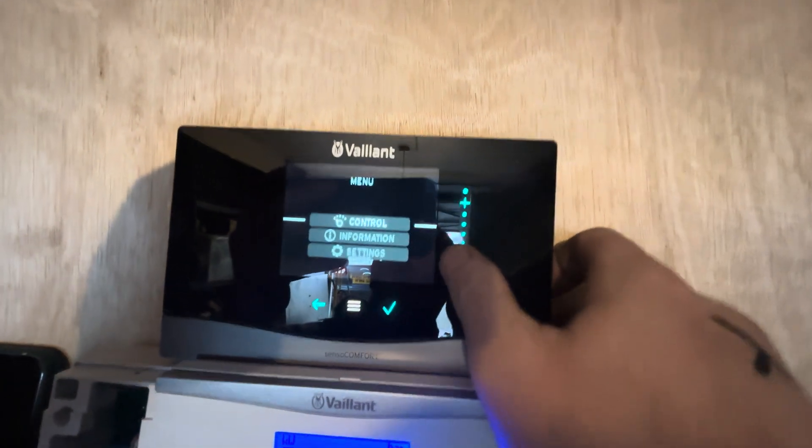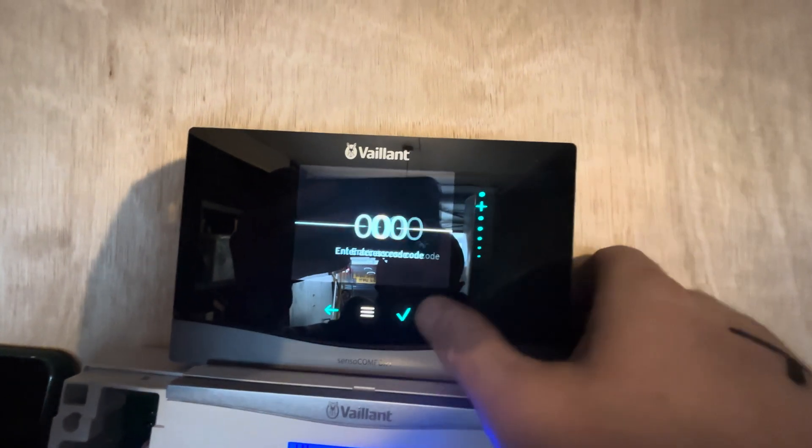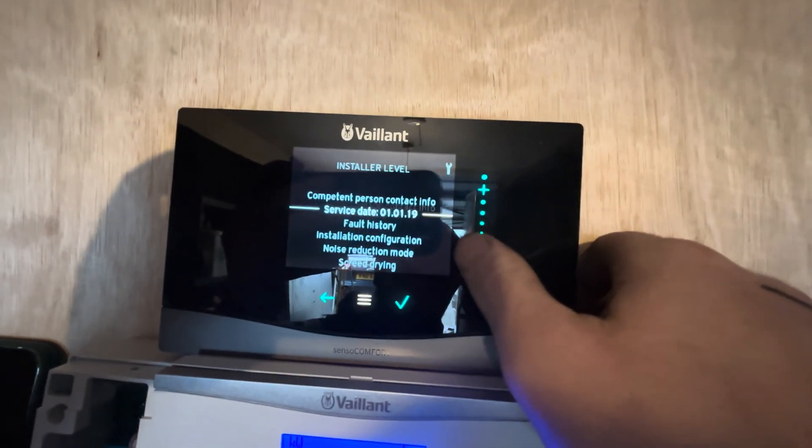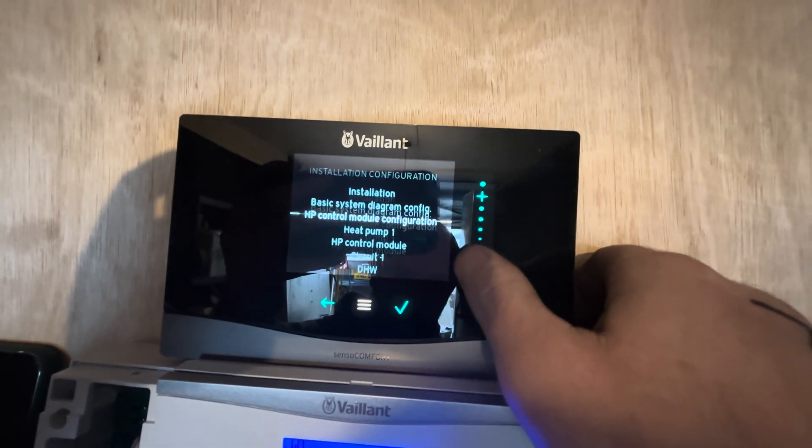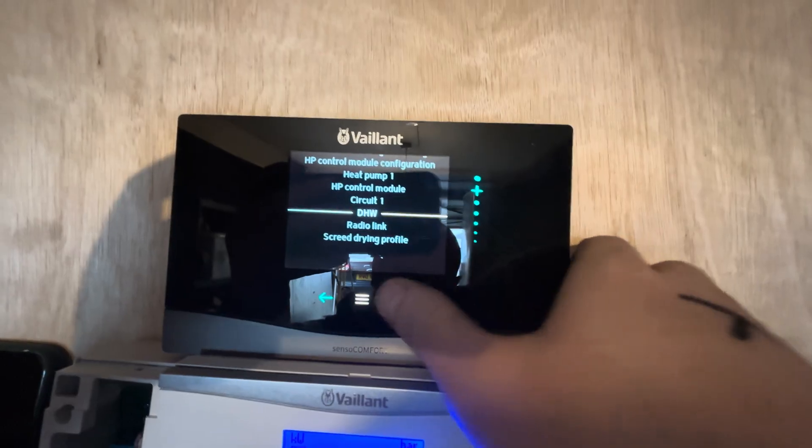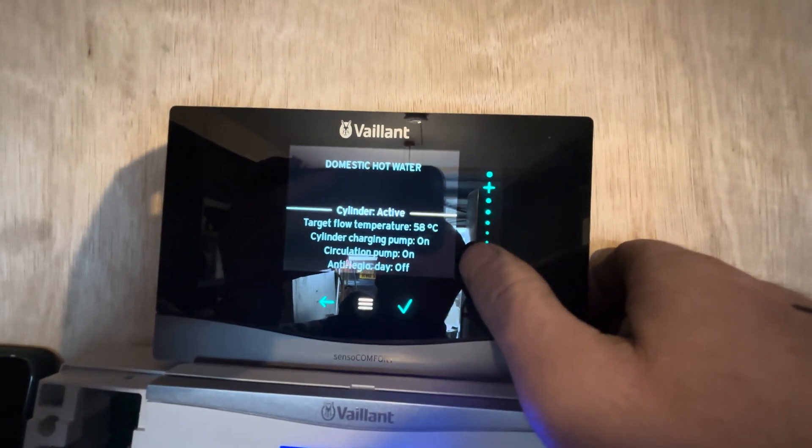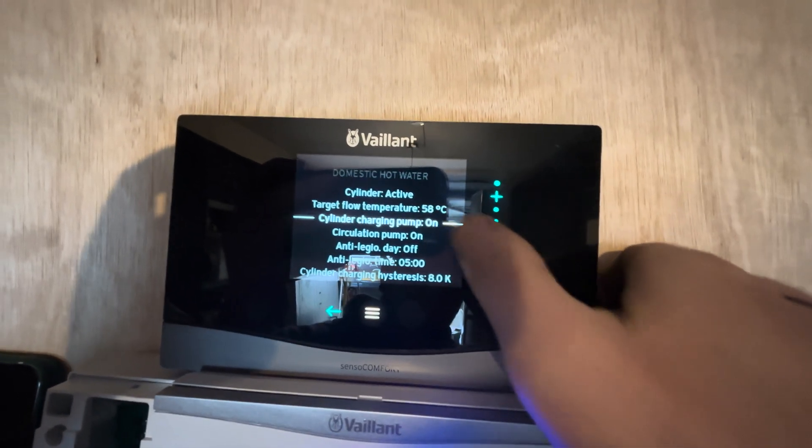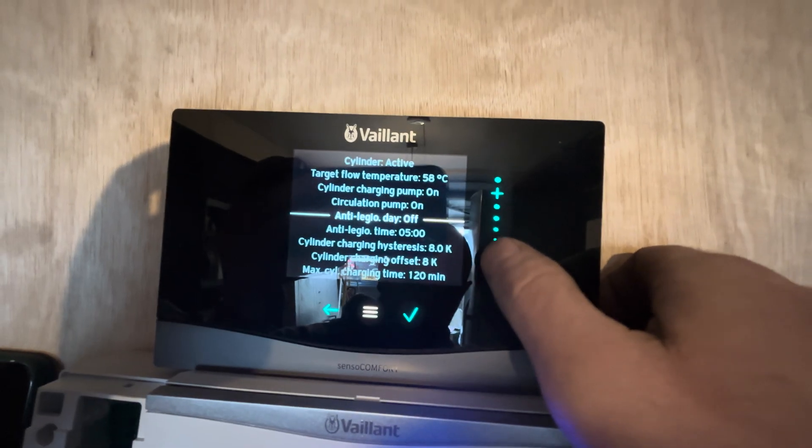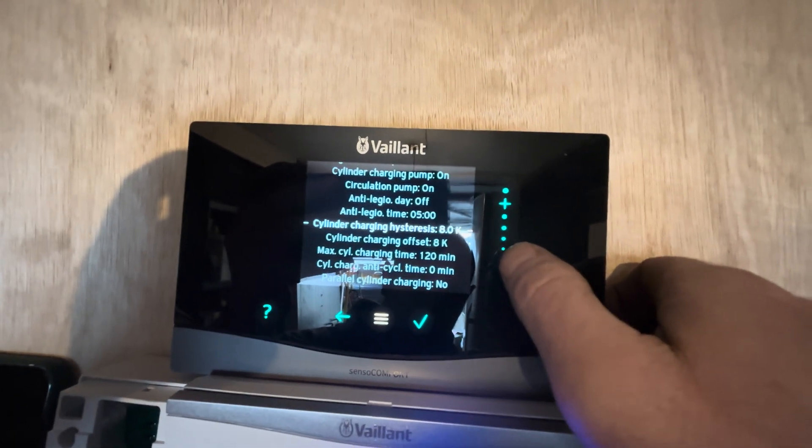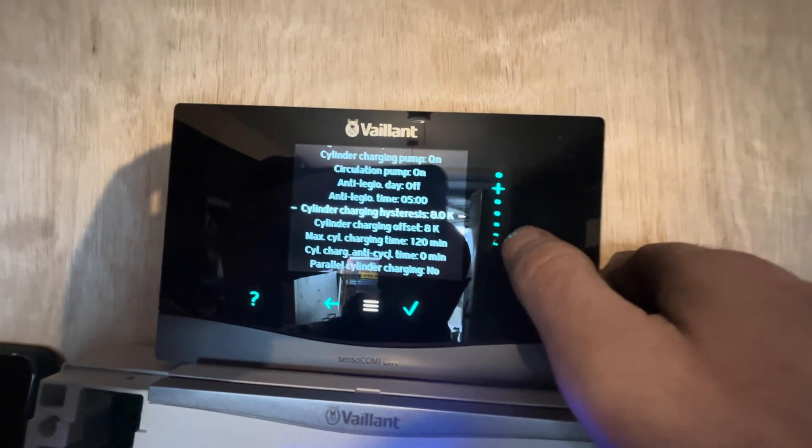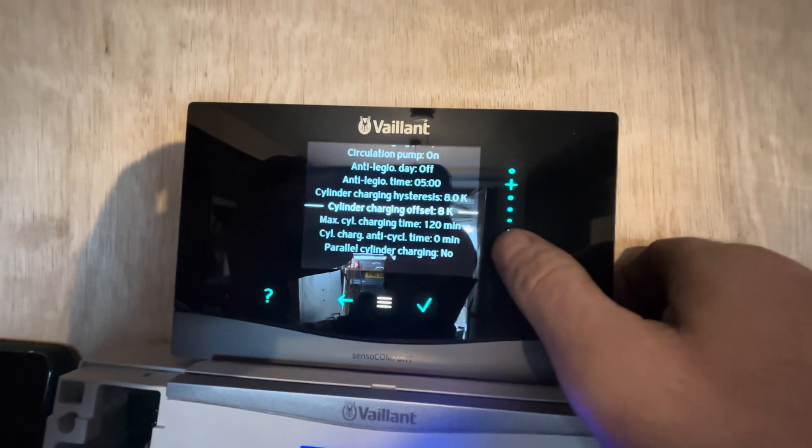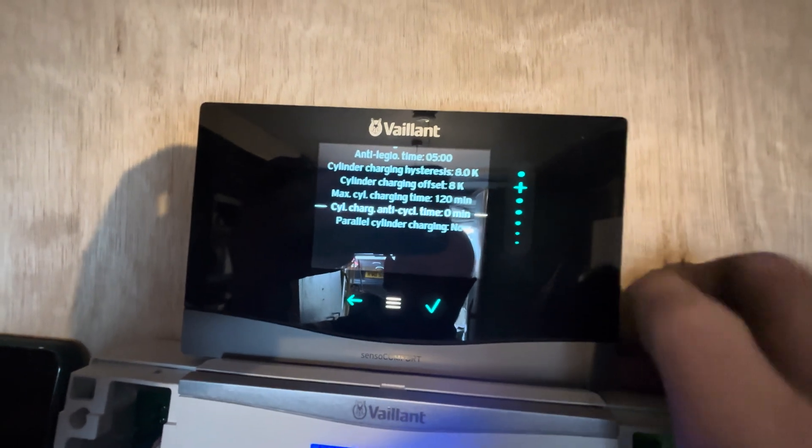Let's go down to the settings, show you what they're set at. So we're looking for a target flow temperature of 58 degrees C, Legionella switched off, charging hysteresis 8K, cylinder charging offset 8, max running time 120 minutes, anticycle zero.